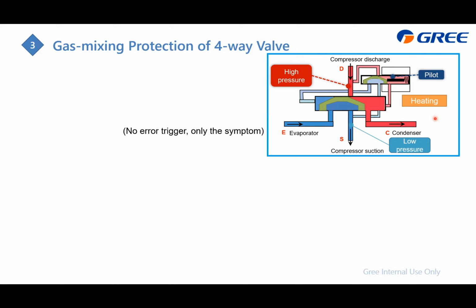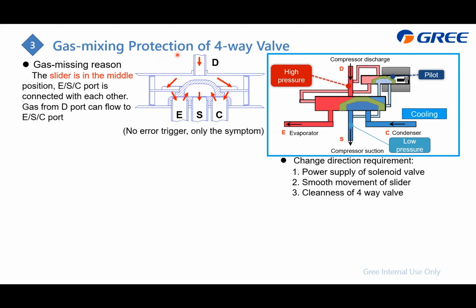direction change. Currently it is in heating mode, because the refrigerant from the compressor will flow to the condenser first. If we need to change it to cooling mode, the system with the 4-way valve will just move like this. You can see that we just move this solenoid valve. Then from here, we use the inside refrigerant pressure to push this slider to the other side. So for this gas mixing protection, that means this slider will stay at this middle position, right? Then the refrigerant from this D port can flow into these 3 pipes, and then there's no heating or cooling.